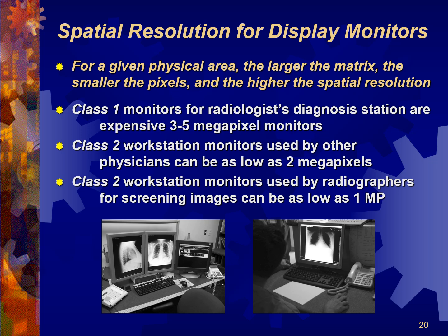Okay? Assessing whether an image is diagnostic and actually using an image for diagnosis, those are 2 different standards. Okay? Class 2 monitors are sufficient to assess, is this image diagnostic or not? So that's why when you're at your workstation, you can expect that it's a class 2 monitor.